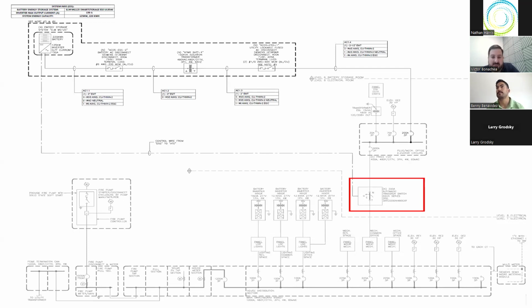Is feeding another distribution board with elevator loads, and one of the breakers on that board is feeding downstream, where it's actually connected to an inverter. Now that's the inverter that they want to be able to operate in grid-tie mode most of the time, and helping feed power to the rest of the system and optimize costs with normal operation when utilities could. But the intention here was that when power fails, the utility power fails, that ATS would provide the isolation so that the elevator board and that inverter are disconnected from the rest of the facility's distribution system, which would then allow that inverter to turn back online in grid forming mode and provide power to the elevator distribution board right there. Unfortunately, it's not going to work.